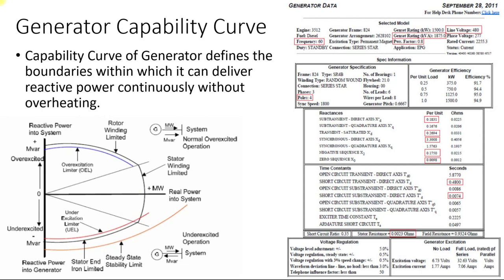How much maximum current can you provide? You can provide current up to the value where you do not hit the rotor winding limit, because when you increase the current in your conductor, heat is generated due to resistance within the conductor. This maximum limit defines how far you can go in the overexcited range. The positive range of reactive power is also known as the overexcited range.